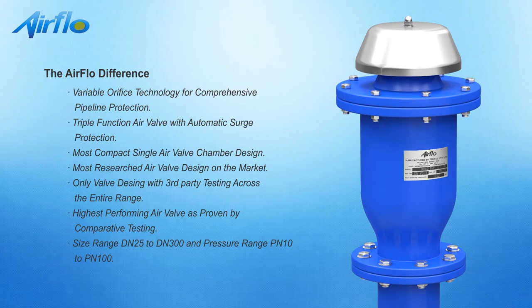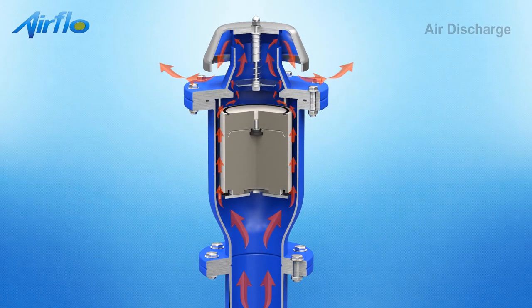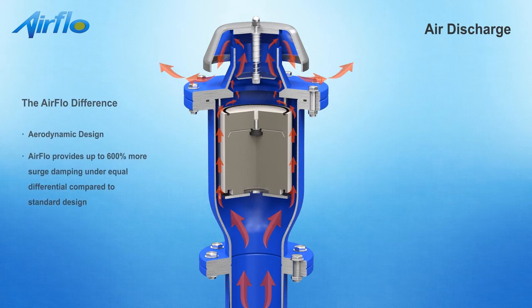This design addresses the demand for an air valve with a multi-adjustable orifice without the limitations of conventional designs. Air enters the valve and flows through the annular space between the floats and the valve body and discharges from the large orifice into the atmosphere. The discharging air immediately impacts the variable orifice shuttle, which rises as the air differential pressure increases across the large orifice. In reaction to increased airflow, the variable orifice shuttle rises further, forcing air through a narrower path.